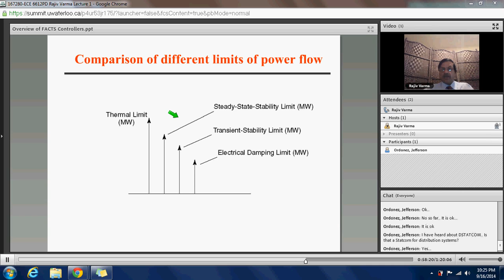They can also prevent loop flows. You remember I talked about the power flowing from Windsor to Toronto, or from Windsor down to Ohio through Niagara Falls and back to Toronto. This is a loop flow. The power has parallel paths, and you would like to avoid that. So FACTS devices are one of the ways of avoiding it. That's one. They can also improve the system transient stability limit. This is another major application of FACTS devices.